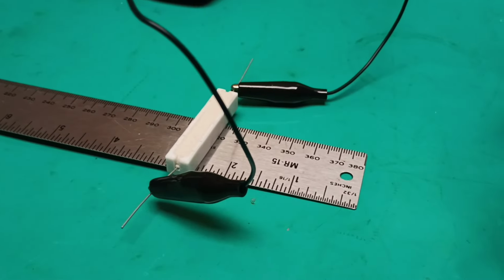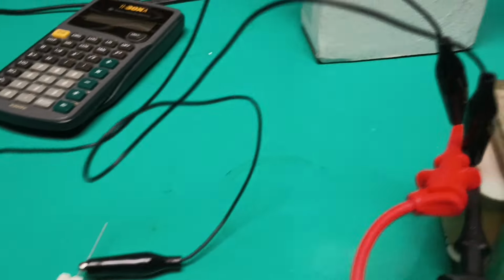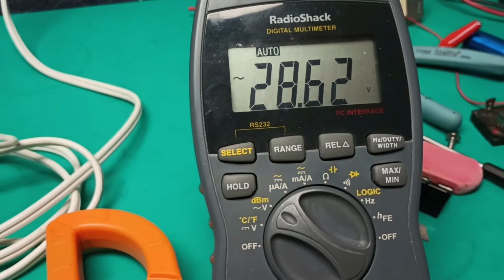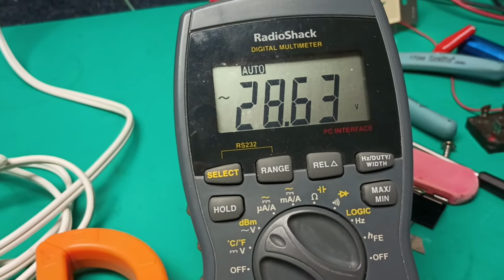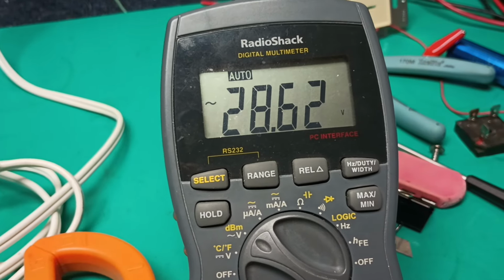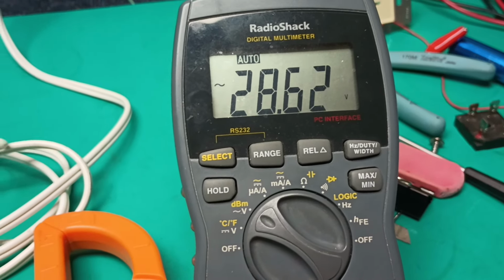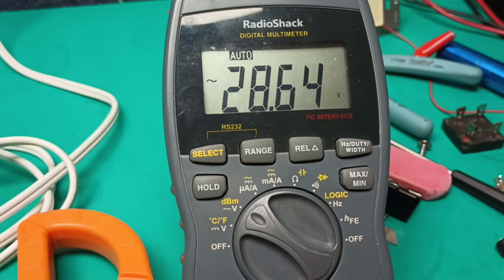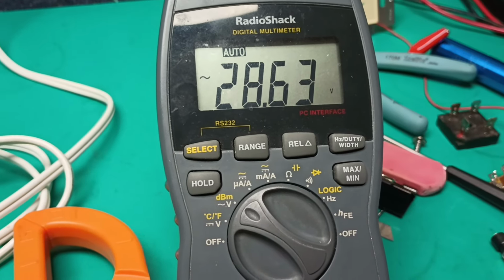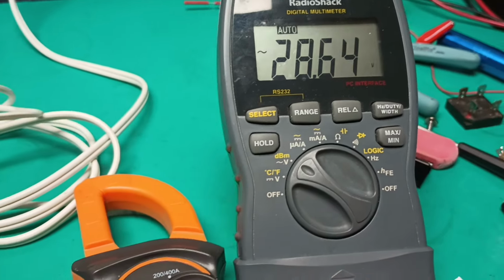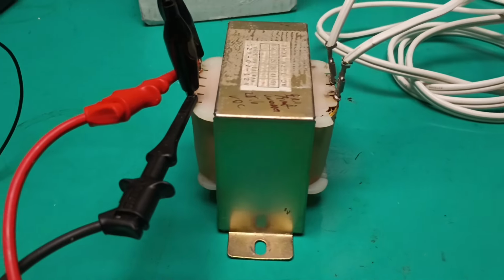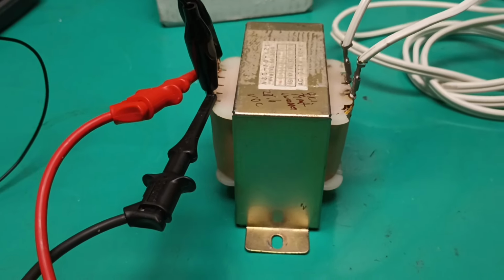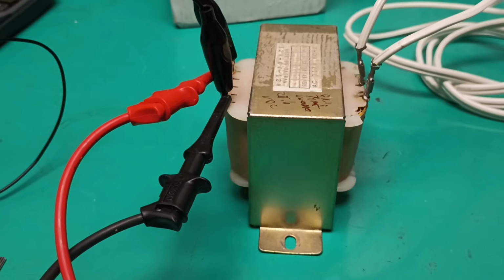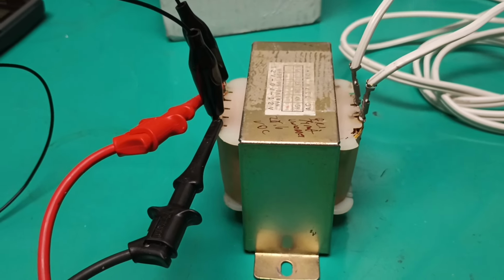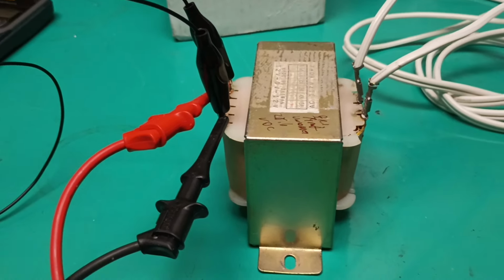Okay, there's a 100 ohm, 10 watt sandstone resistor connected to the secondary, and the secondary voltage is 28.63. It dropped about 0.2 of a volt. That is extremely good regulation. This is what you might call passive regulation. It's not a transistor voltage regulator. That regulation comes from the transformer being very much oversized for the load. A much smaller transformer, volt-amp wise, would have a much bigger drop.